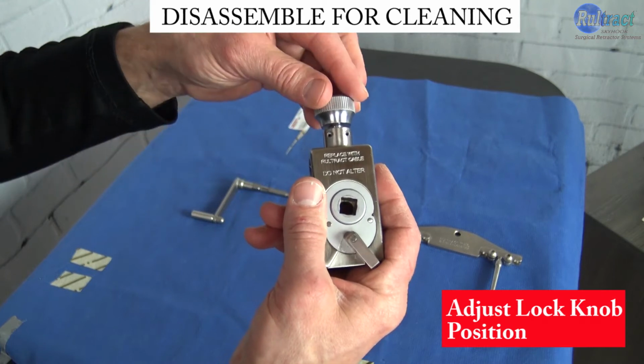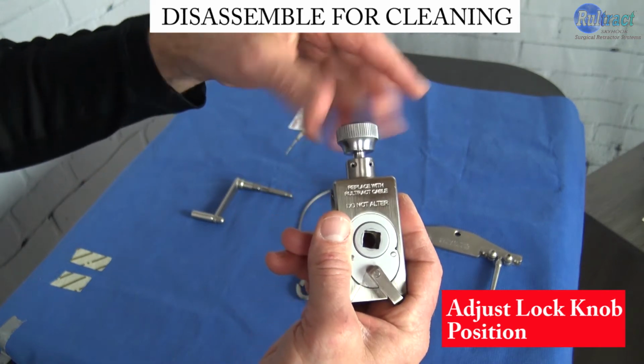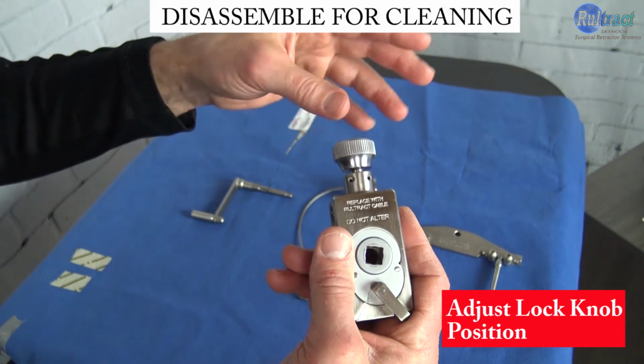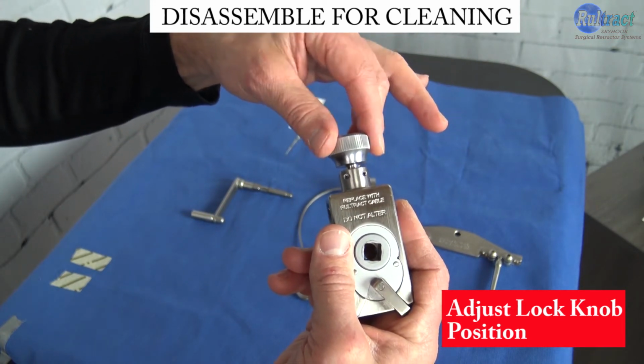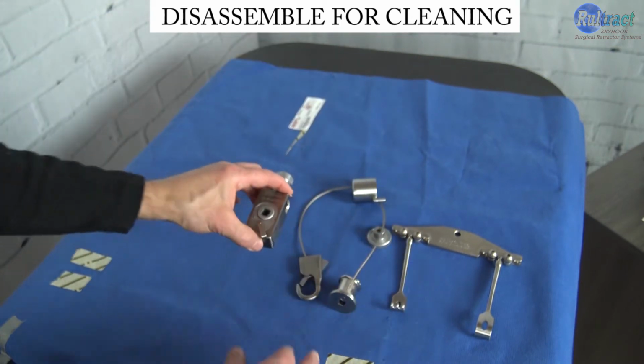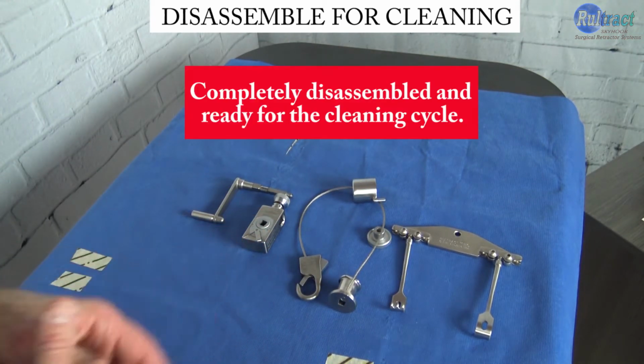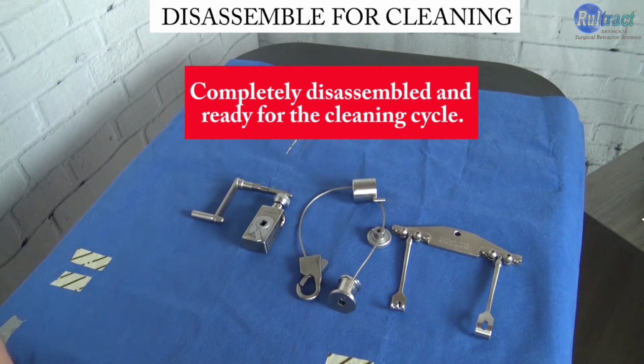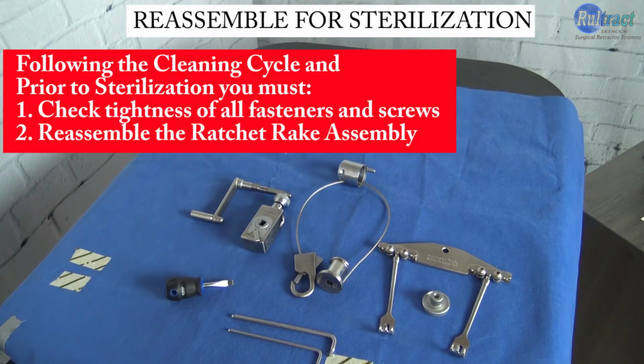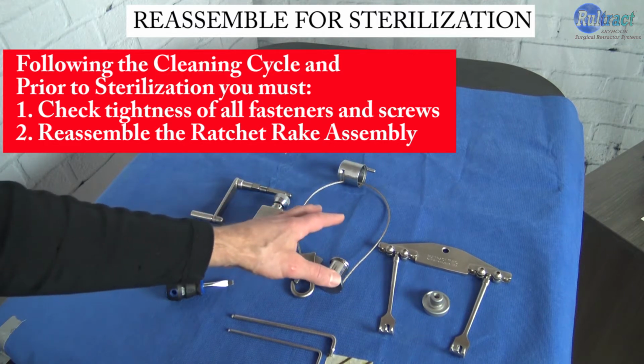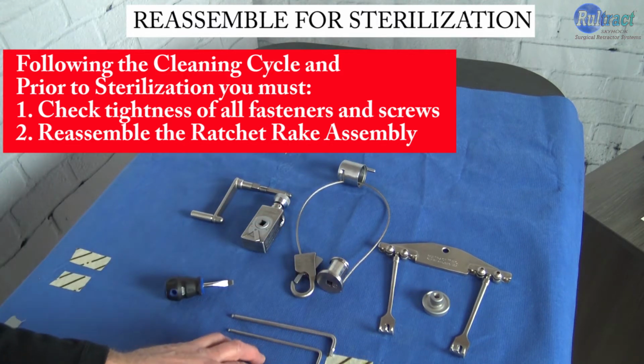Next, you're going to be sure that your lock knob is not closed all the way or opened all the way. You want it somewhere right in the middle so that it has some play in it. Now your Rultract ratchet rake assembly is completely disassembled and ready for the cleaning cycle. Following the completion of the cleaning cycle, we are now ready to check for tightness of all fasteners and screws. Now you can see that we disassembled the Rultract ratchet rake assembly into 5 pieces for the cleaning cycle, and we are now ready to reassemble those 5 pieces for sterilization and use.